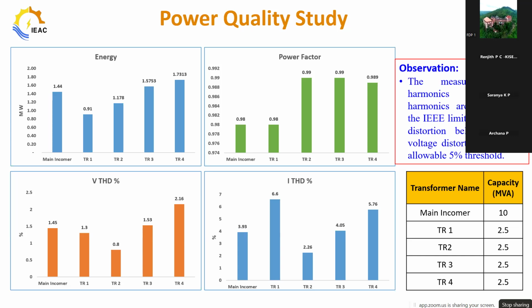Normally there are IEEE limits for each part, like the incomer of the transformer, specifying the maximum limit for harmonics. That limit is checked in the industry to see if it is below or above the value. Accordingly, we give recommendations or adjustments. Sometimes it varies depending on the quality of the grid supply, since in some areas the grid supply may not be good quality.